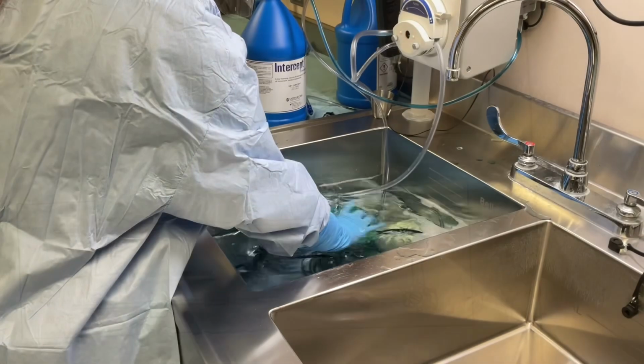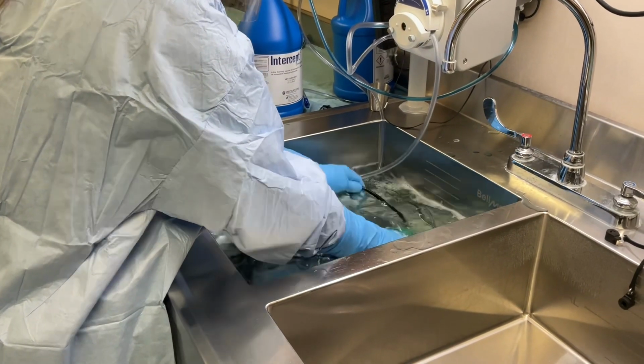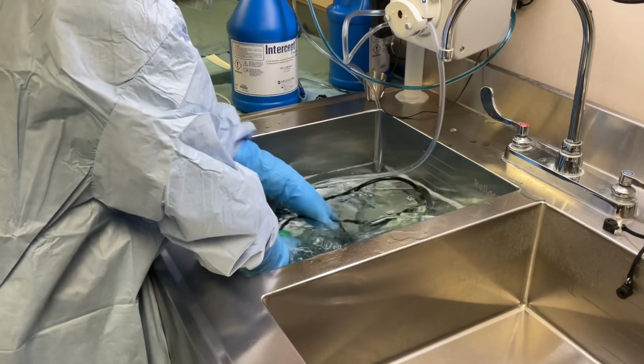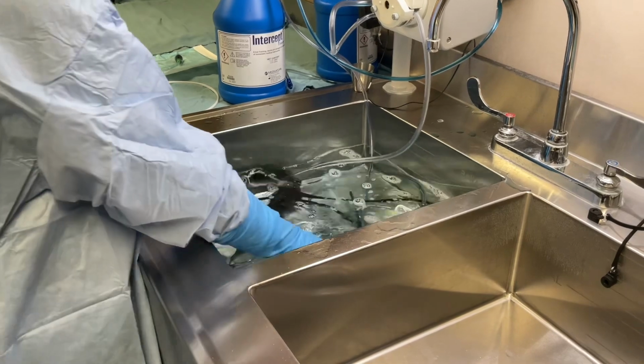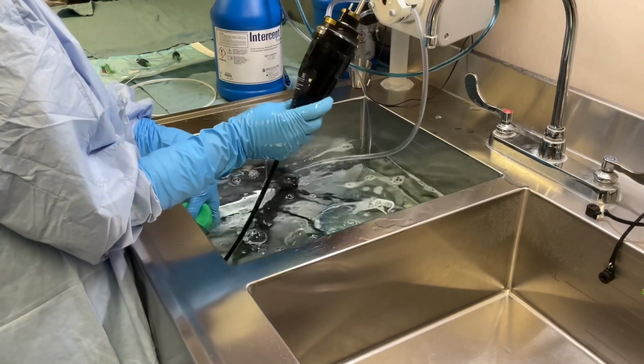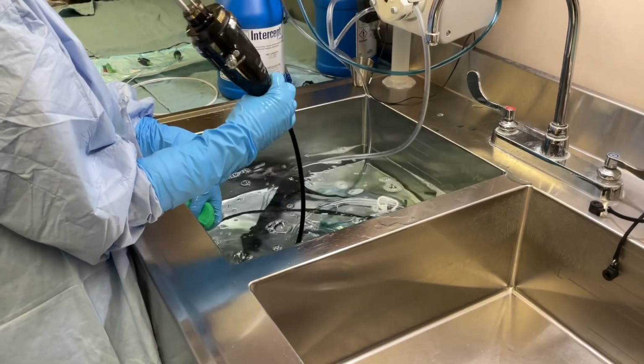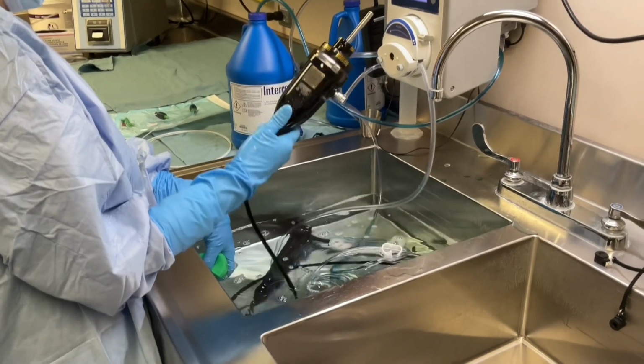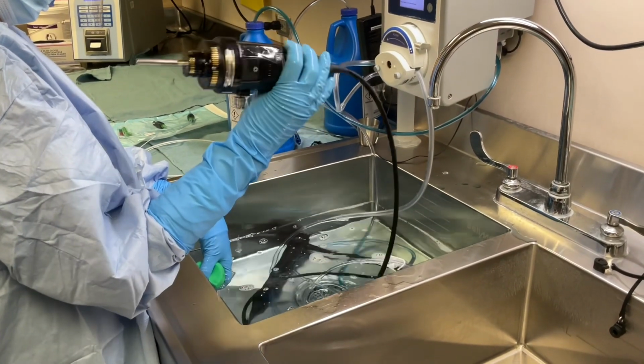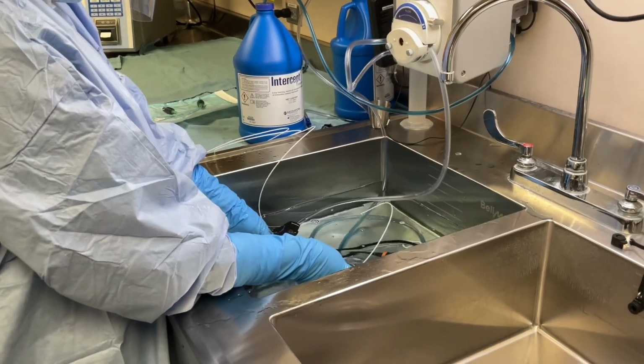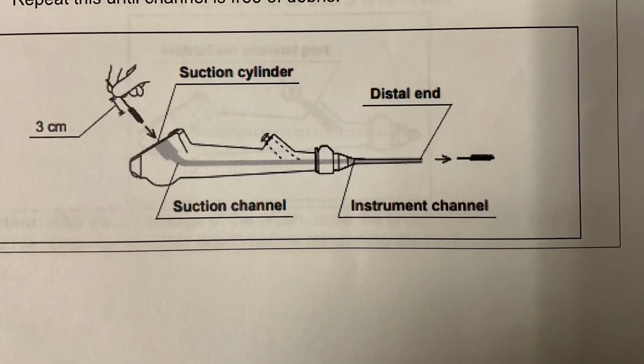While immersing the endoscope completely in the detergent solution, thoroughly wipe all external surfaces of the endoscope connector and the universal cord using a lint-free cloth or sponge. Verify that no debris remains. If so, repeat steps. Brushing suction cylinder channel.